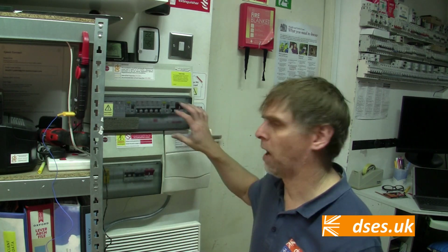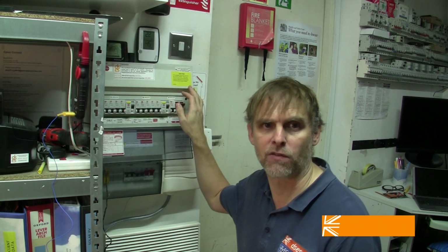For example, on a wholly new circuit on which AFDD protection is required, but where you're not tasked with changing out the existing CU. The aim then is to depopulate this upper board from its current dual RCD high integrity configuration, link the 3 neutral bars together as one, replace the 3 busbars for a single one, and to populate it with my 9 AFDDs.